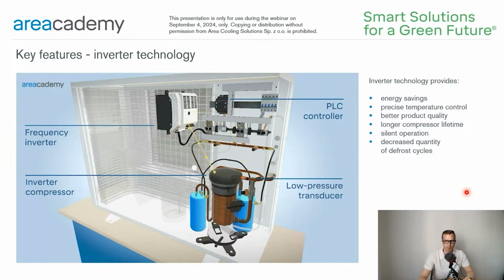power consumption. Summing up, inverter technology provides energy savings because there are fewer compressor start and stop cycles and fewer required defrost cycles, with operation in a wide capacity range. Better product quality, thanks to the stepless regulation adapting the capacity to the current installation demand. Inverter technology guarantees precise temperature regulation, ensuring the increased quality of the stored product. It also provides longer compressor lifetime because there are fewer on-off cycles and soft starts. And finally, it provides silent operation, thanks to the decreased noise level in part load conditions.